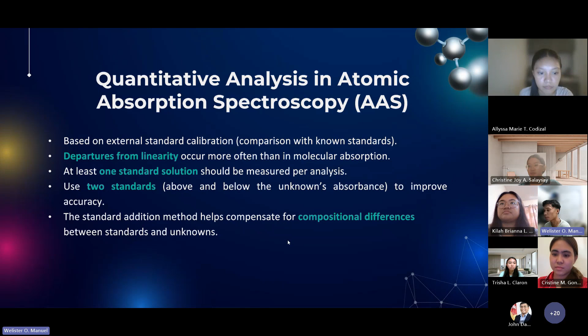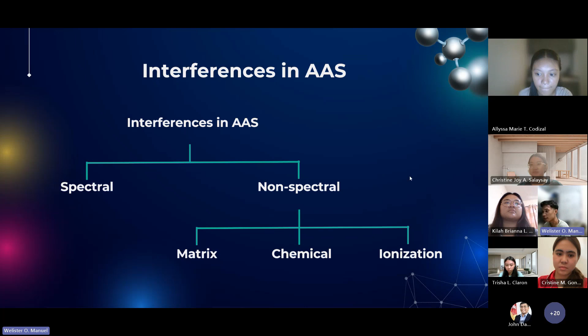So for quantitative analysis in atomic absorption spectroscopy, the standard addition method helps compensate for compositional differences between standards and unknowns. And we usually use two standards above and below the unknown absorbance to improve our accuracy during our data analysis. And for interferences in AAS, we have two types of interferences, the spectral and the non-spectral. And non-spectral is composed of matrix, chemical, and ionization.